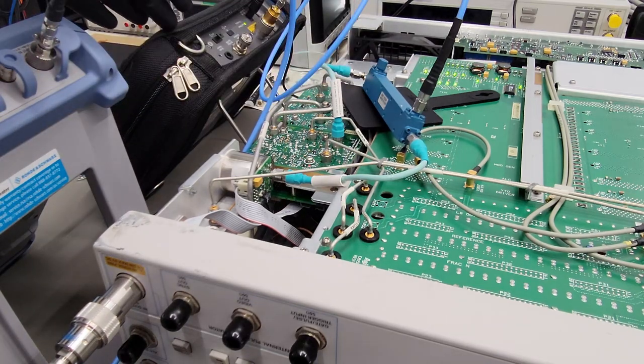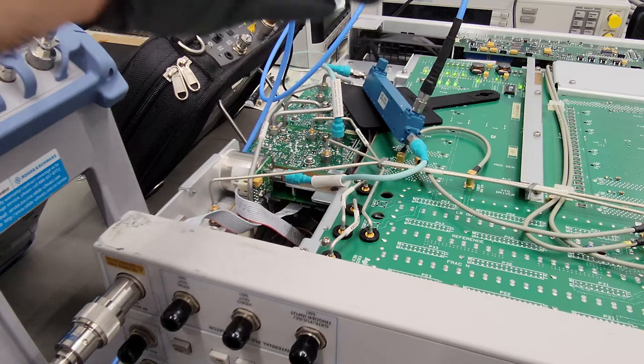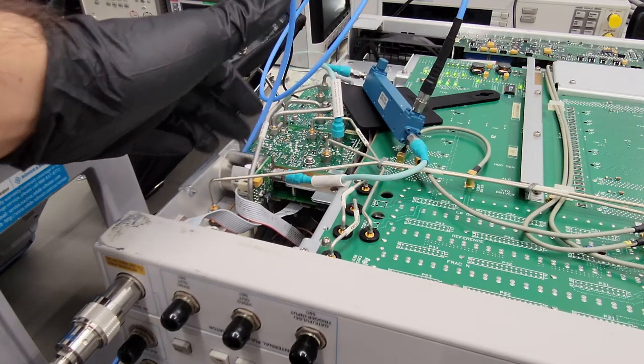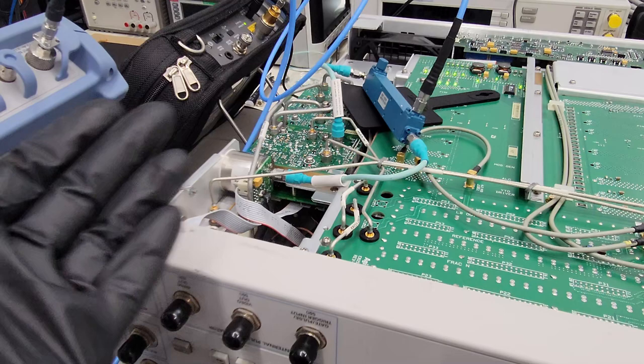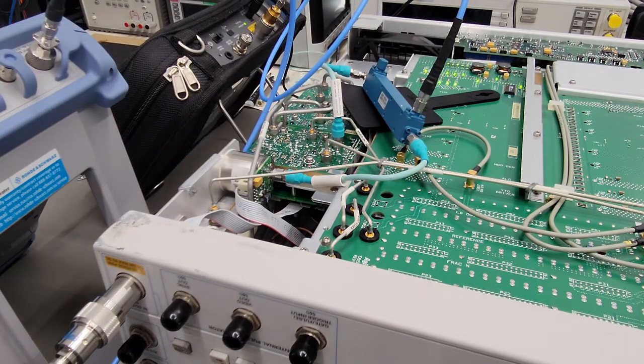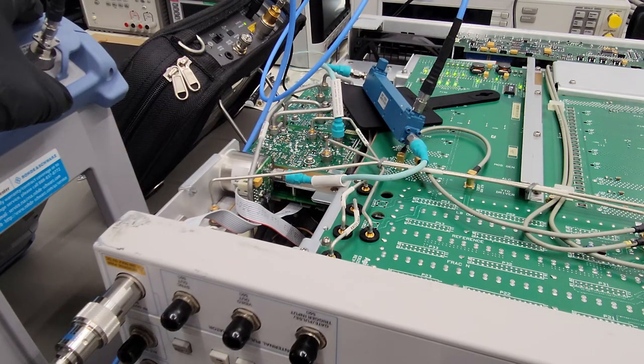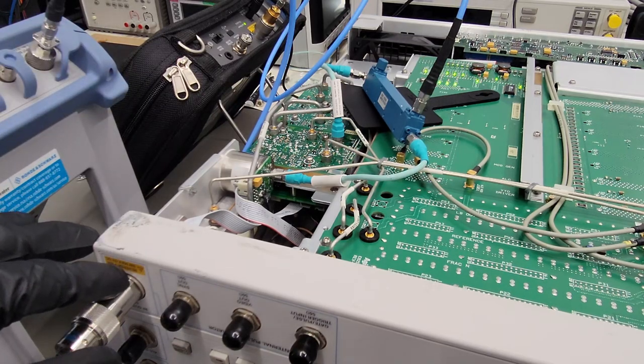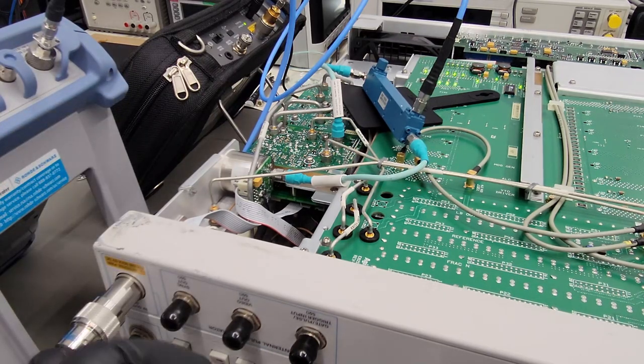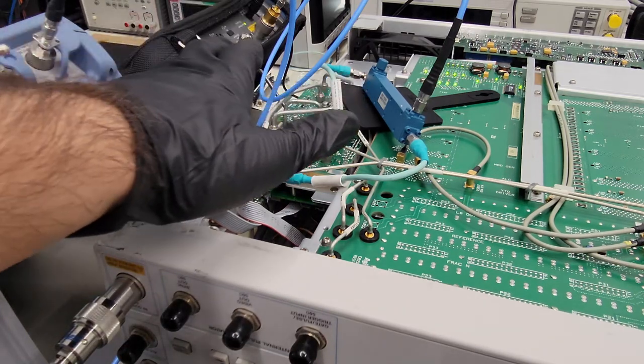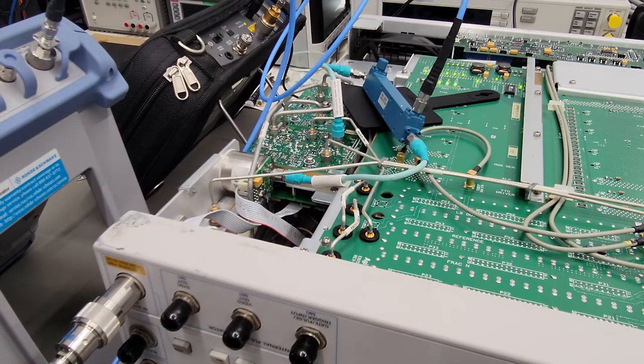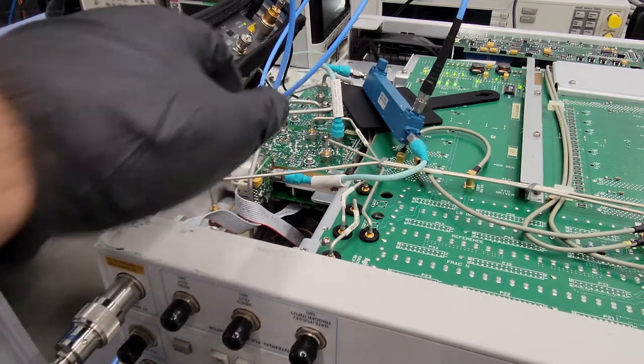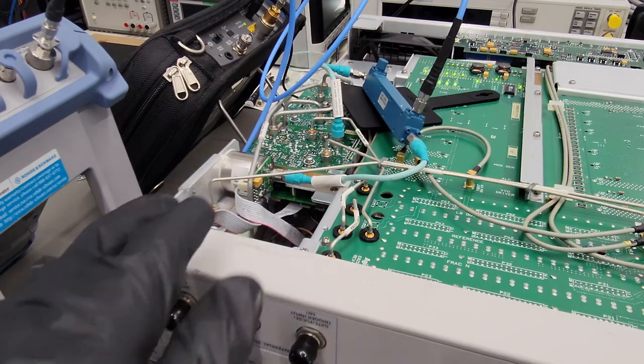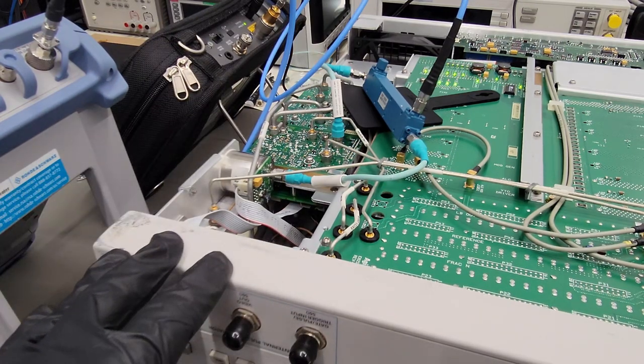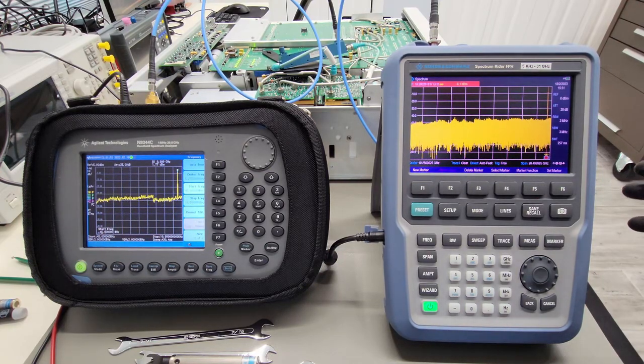So the signal we view on our spectrum analyzer here should be representative of what's coming out of the YIG minus approximately 10 dB, because that's the loss from the coupling. And then, of course, we have another spectrum analyzer here attached to the output, so we can also, at the same time, change the frequency on the instrument, view what the YIG is putting out, and then what the output looks like as well, just to make sure that everything is tracking. So let's take a look at our two spectrum analyzers as we change the frequency and amplitude on the instrument and see what happens.